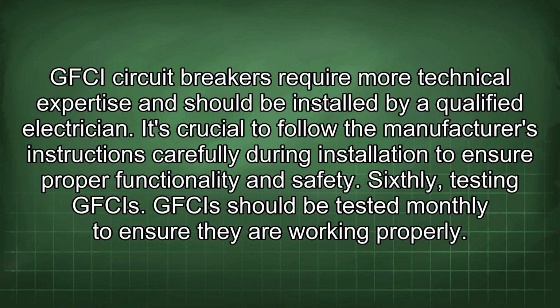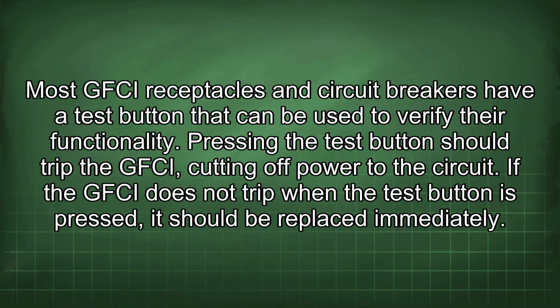Sixthly, testing GFCIs. GFCIs should be tested monthly to ensure they are working properly. Most GFCI receptacles and circuit breakers have a test button that can be used to verify their functionality. Pressing the test button should trip the GFCI, cutting off power to the circuit. If the GFCI does not trip when the test button is pressed, it should be replaced immediately.